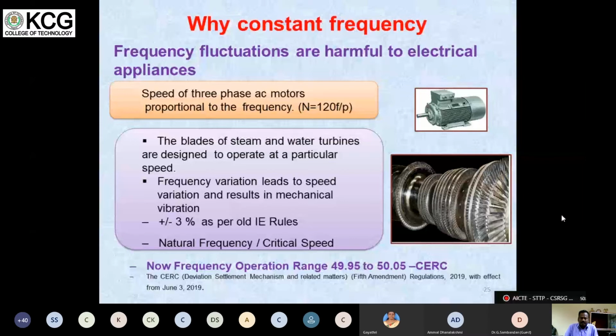So as per both conditions, consumer side and utility or generator side, we have to maintain the frequency. With the frequency higher, the turbine will have problems. With the frequency lower, again we will have problems in the turbine. It is not a big problem for the generator side, but it is a problem for the mechanical equipment, the turbine. Due to centrifugal force, blades will get damaged. At lower frequency, due to vibration, the turbine will get damaged. So plus or minus 3% is the safe operating region. As per the old IE rules, Indian Electricity Rules, any equipment can be operated at plus or minus 3%. That is 48.5 to 51.5 hertz. That is the safe operating region.